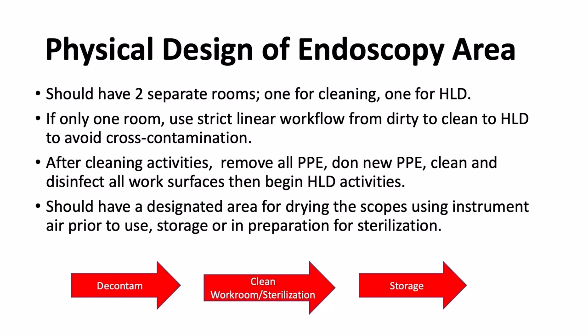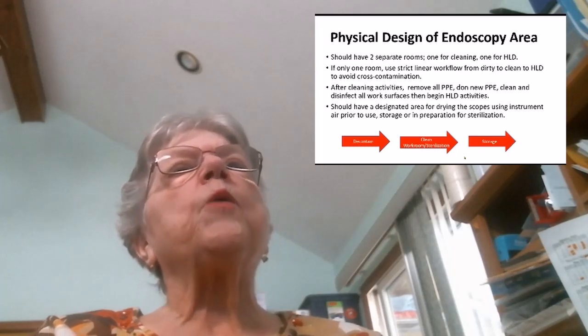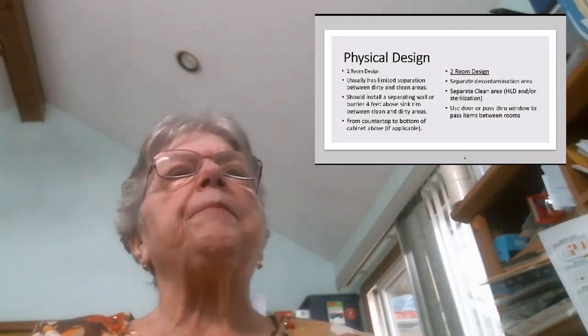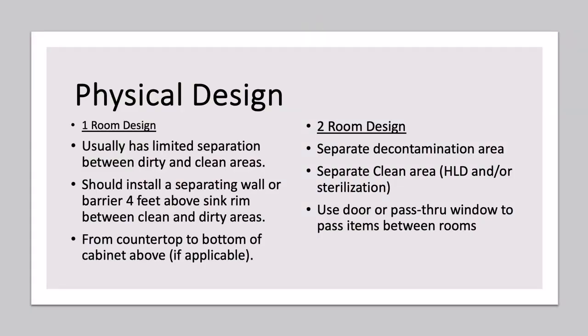And you should have a designated area for drying the scopes using instrument air prior to use, storage, or in preparation for sterilization. In a one-room design, you usually have limited separation between dirty and clean. In that one-room design, you should install a separating wall or barrier 4 feet above the sink rim between the clean and dirty areas. Or it can go from the countertop to the bottom of the cabinet above, if applicable. In a two-room design, you have a separate decontamination area. You have a separate clean area where high-level disinfection or sterilization occurs. You can use a door or a pass-through window to pass items between the two rooms.